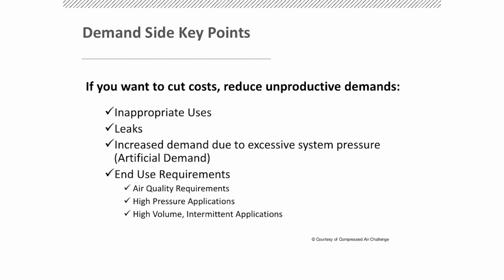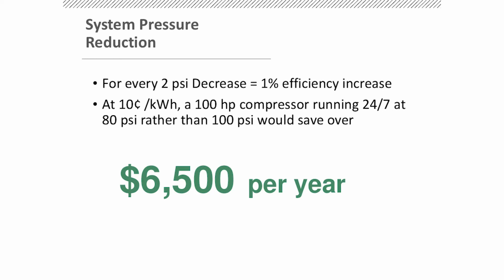Because again, I just mentioned that 2 psi equals 1% efficiency. If I can reduce those pressure drops and lower my pressure, I get energy efficiency. I get energy savings, okay? So to give you an example, at 10 cents a kilowatt hour for a compressor running around the clock, a 100 horsepower compressor running at 80 PSI versus 100 PSI will save over $6,500 a year just in reducing that amount, okay? Because again, that's the cost it's going to be to operate that at a higher pressure.